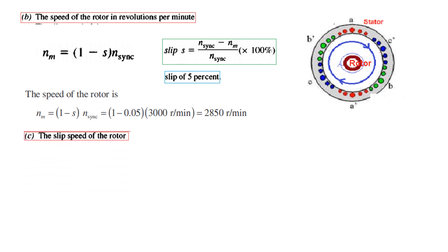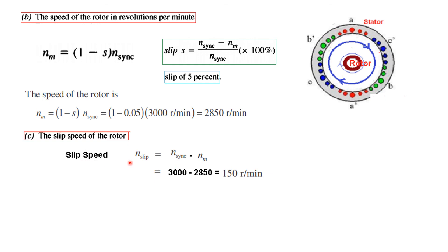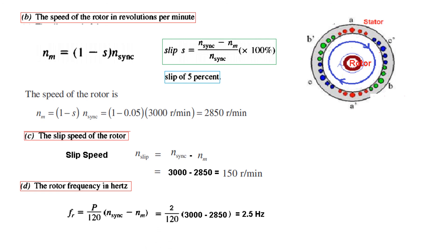Part c asks for the slip speed of the rotor — the speed at which the rotor is slipping behind. The slip speed N-slip equals N-sync minus N-motor, which gives 150 RPM. Finally, part d asks for the rotor frequency in hertz. Applying the formula F-r equals P divided by 120, times (N-sync minus N-m), and substituting the values, the rotor frequency is 2.5 Hz.